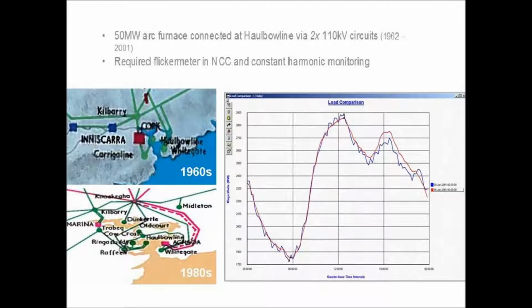The plot on the right shows basically what Irish Steel did to the load in Ireland. The red line is the week after Irish Steel was decommissioned, and the blue line shows the effect of that 50 megawatt arc furnace and the 12 megawatt ladle on the system when it was constantly turning on and off. It would cause the load to jump up or down at a given time, which is fairly hard to manage, and frequency obviously would jump along with it.